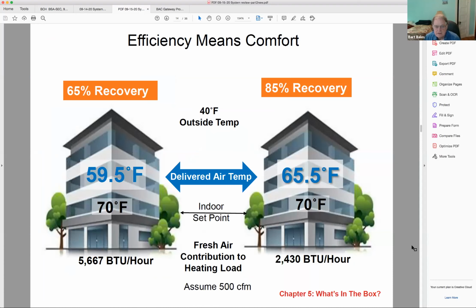One of the advantages that I was mentioning to using higher efficiency heat recovery is the temperatures that result for the higher performance one. Notice that on the left-hand side, the typical cross-flow heat exchangers that many more typical heat recovery ventilation systems use only bring the temperature back up a certain amount. At 40 degrees outside air temperature, you'd be bringing air in at a little less than 60 degrees, whereas with the counterflow heat exchanger, you'd be bringing it in at almost 66 degrees, which is very close to the room temperature. Notice that there's a significant difference in the amount of energy saved in doing this as well.